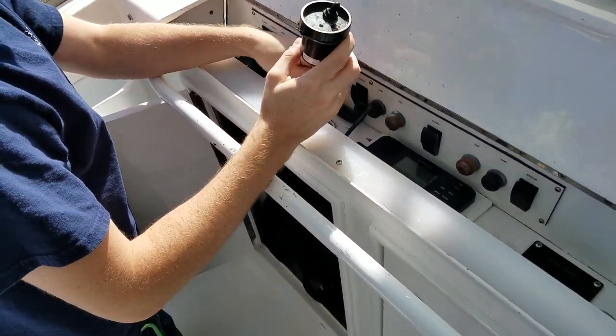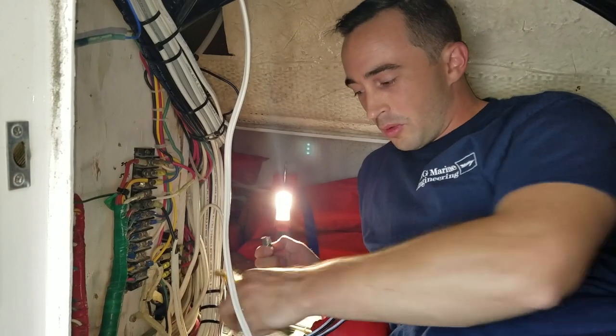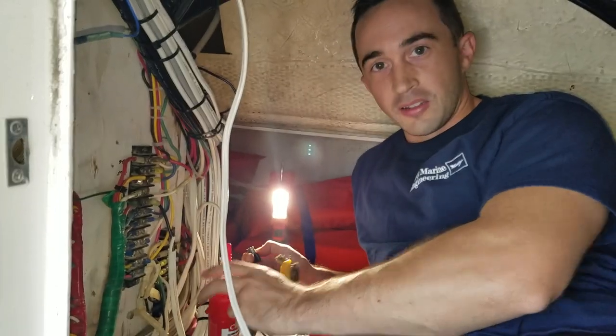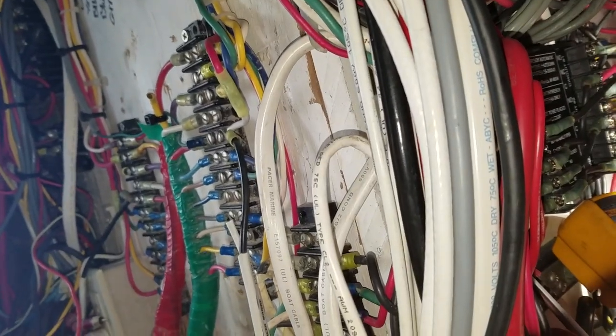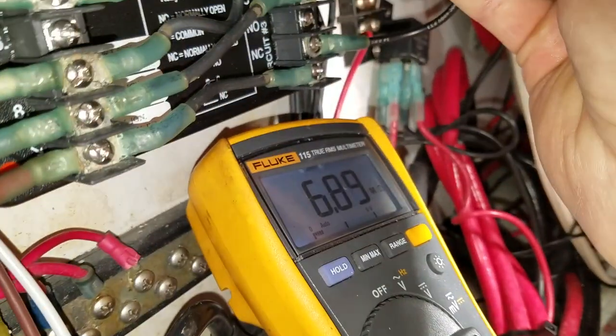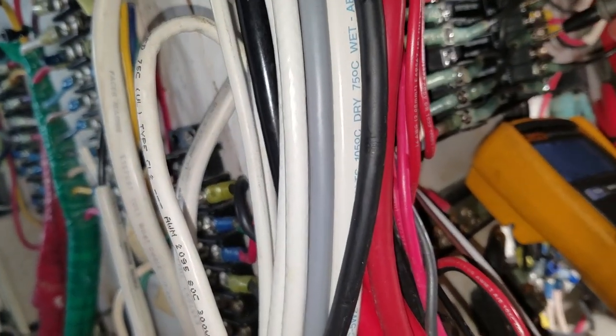Rich is going to pull out the wiring harness — it's plug and play, simple enough. We pull the old one out and drop the new one in. We're all done wiring the board up. The last thing is to connect the harness to the readout display. There's a little bit of corrosion on the plug, so we're going to wire brush it up, put a little dielectric grease on the connection, and then we should be good to go. With everything wired up, we do a quick ohms check across the relay and we're showing 7 megaohms, which is open — exactly what we want.